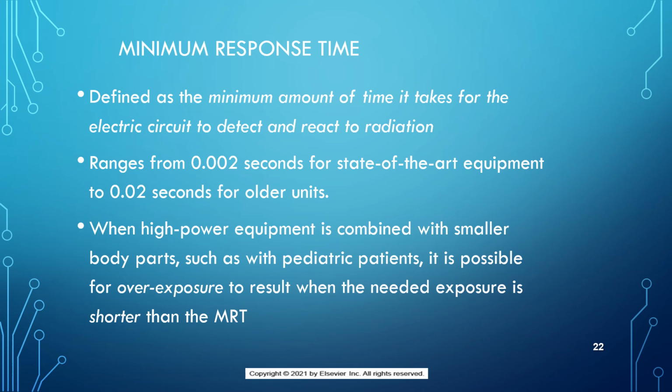And so because of the reaction time of the AEC circuit for very, very rapid exposures, the AEC is not recommended, because it can't turn off the circuit. It can't terminate the exposure fast enough. The transistor has lag. It takes time for the transistor to cut the exposure.